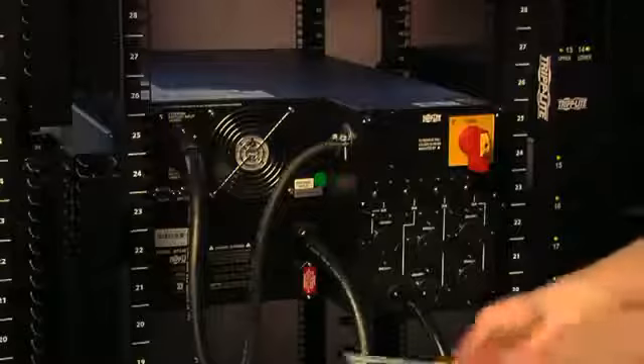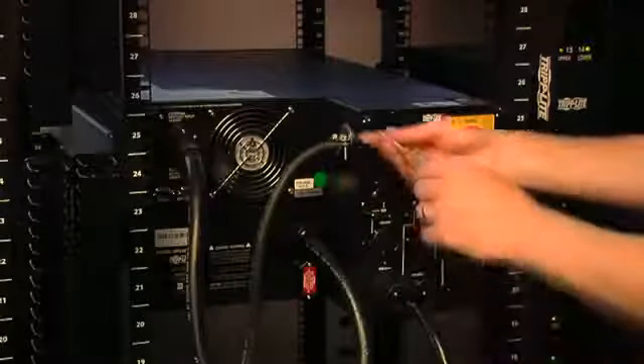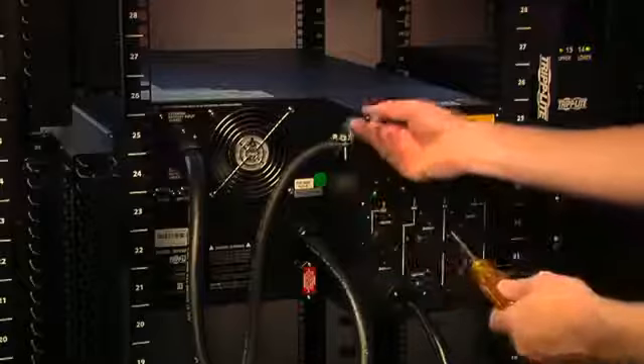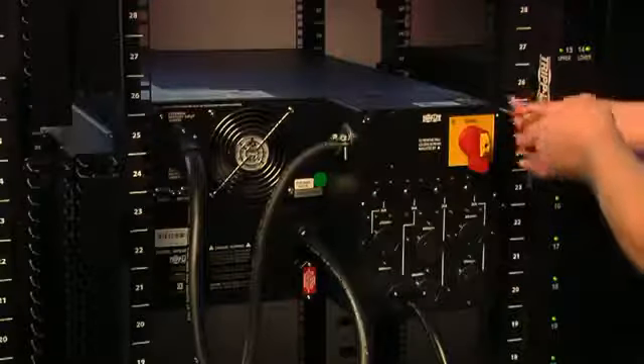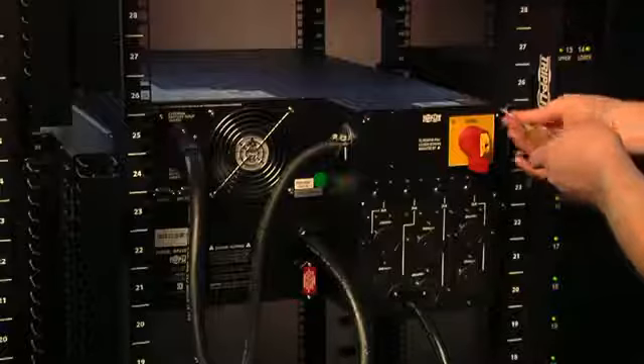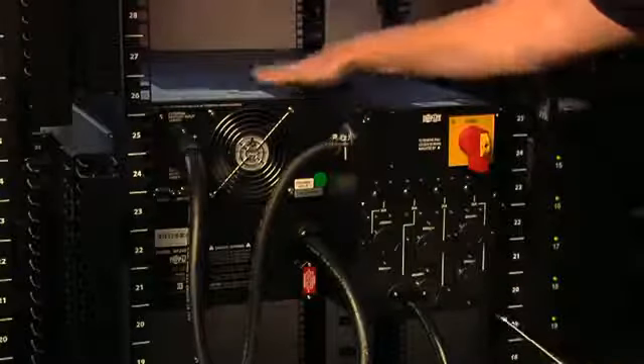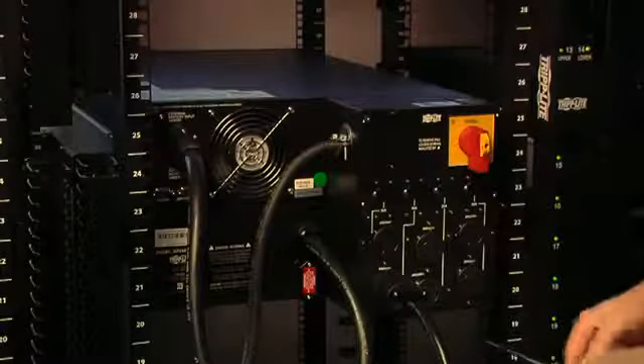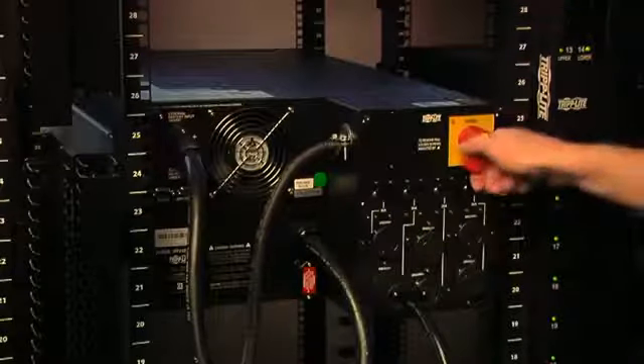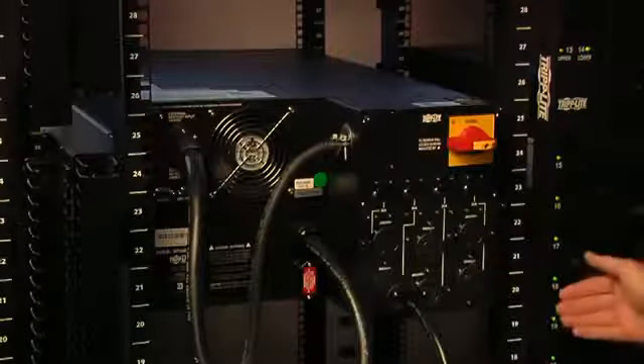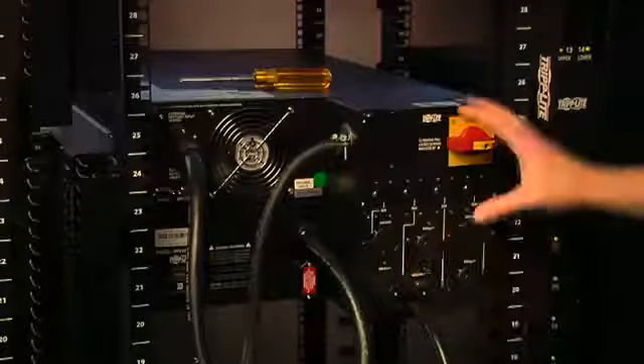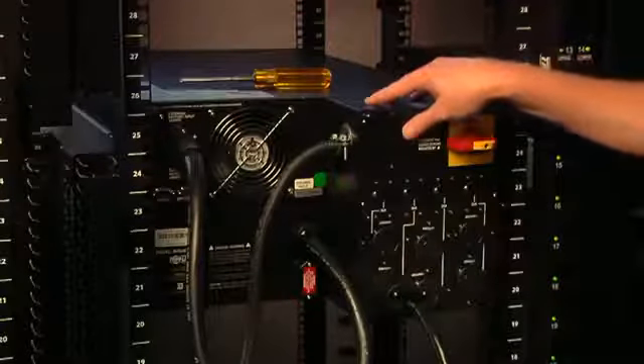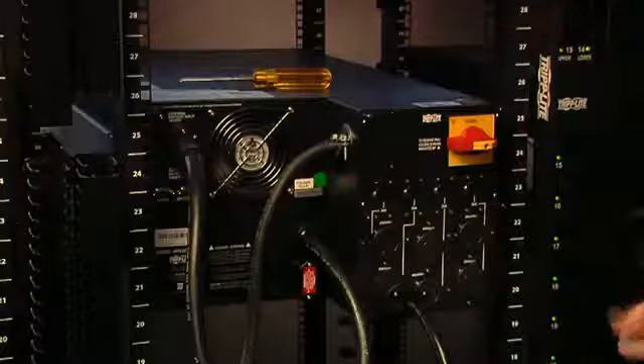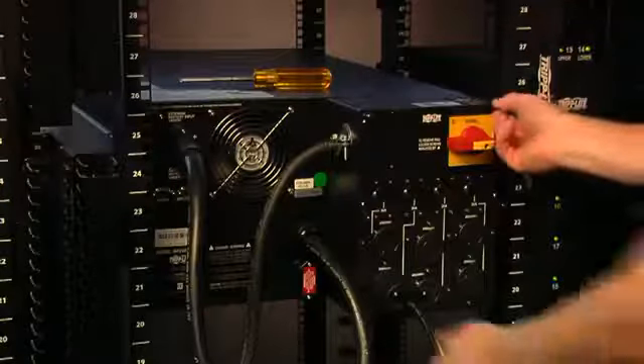With the system now in bypass and equipped with a screwdriver, I can loosen the 4 screws, 3 of which are already loose. These screws connect the PDU physically to the power module. Once that's done, I can rotate this switch to a bypass state, and you'll see all of the load lights remain powered and on. At this time, all the input and the output is happening within this maintenance bypass box, and I can detach the box from the power module itself.